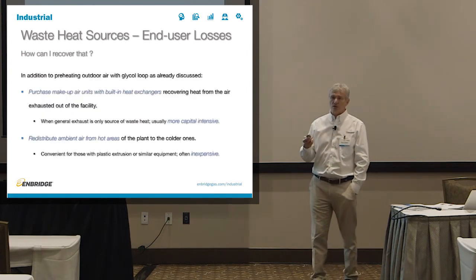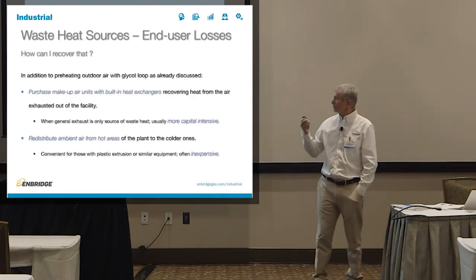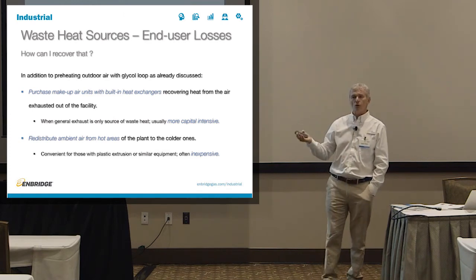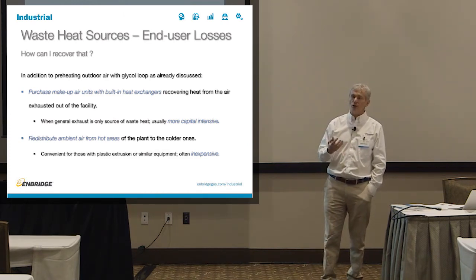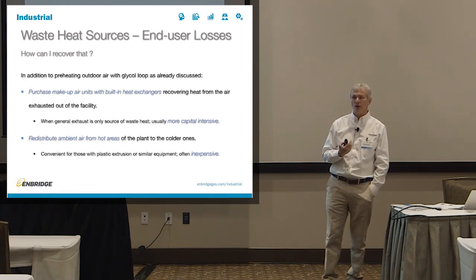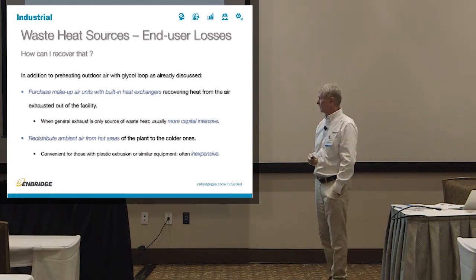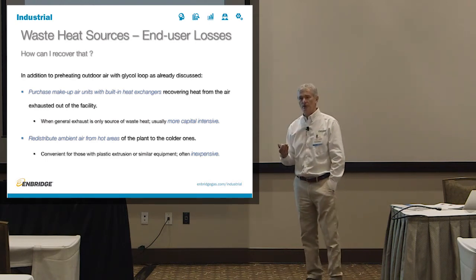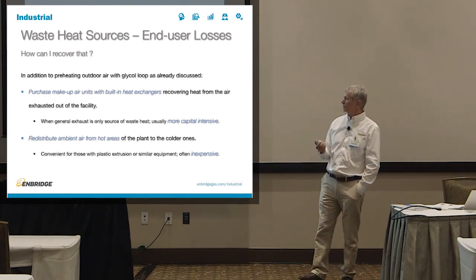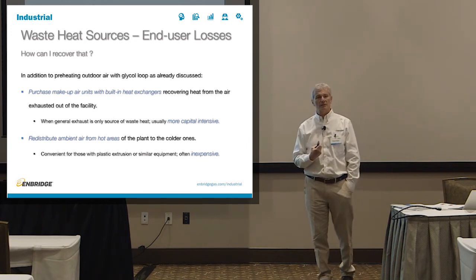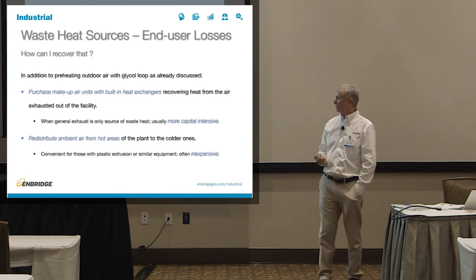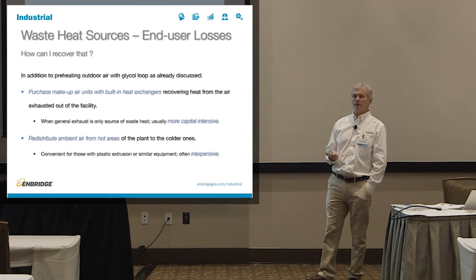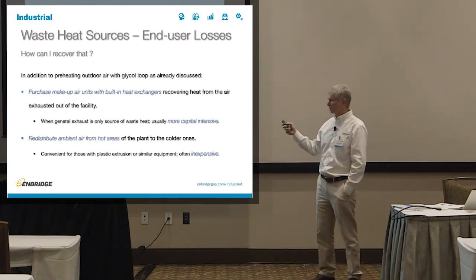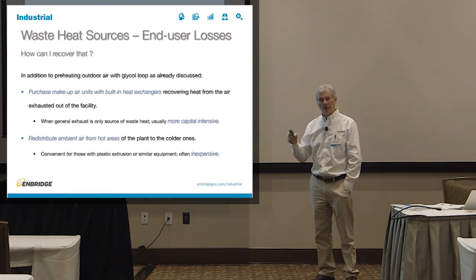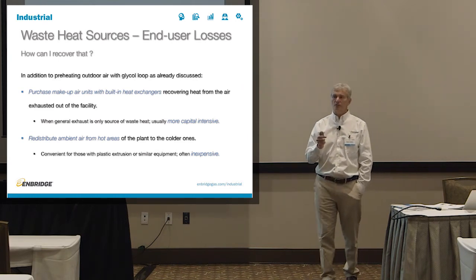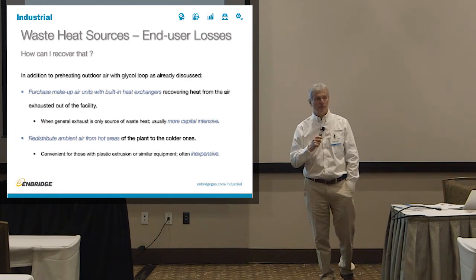So what are the other options? If you have no facility, no way of doing the glycol loop, for example, or you don't want to do it, or you don't have any process heat that generates any heat for the glycol loop to begin with, what other options do you have? Well, now you're talking about purchasing makeup air units. New makeup air units that recover the heat from the facility, or redistributing ambient hot air inside the facility. So we'll talk about the second one first because it's applicable and it's an inexpensive way of heating your facility.